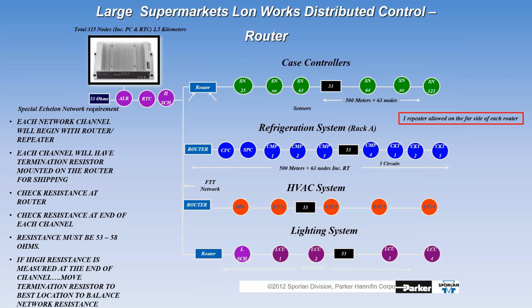In that little bar I showed earlier, which I think Nate asked about, we also have a network analyzer. We always tell our integrators to check the network before leaving the job. In Echelon, a network rating of 25 or 30 is considered good, but we want our network to check in the lower single digits, a 2, a 3, a 5, as close to 0 as possible. When you get close to 0, that means the nodes aren't clogging up with over-communication.